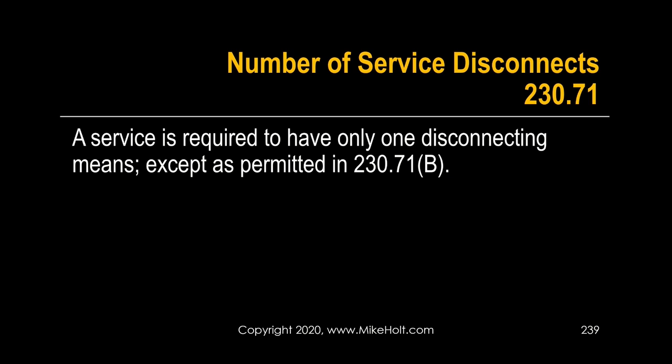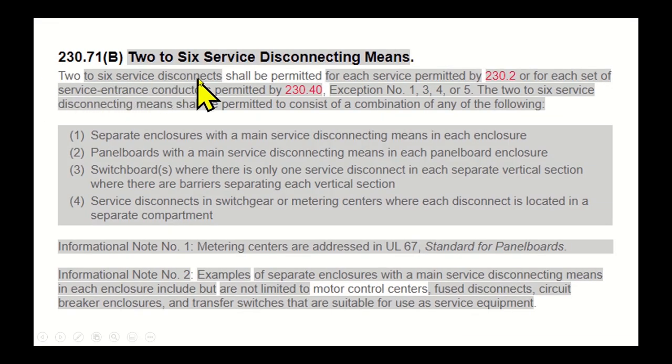Regarding the number of service disconnecting means: 230.71 says a service is required to have only one disconnecting means except as permitted. 230.71(B) says up to six disconnecting means shall be permitted for each service permitted by 230.2, and for each set of service entrance conductors per 230.40 exceptions one, three, four, and five. Services shall be permitted to consist of a combination of any of the following.